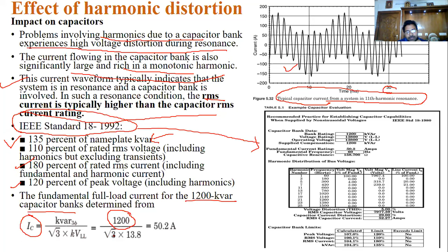So kVAR in 3-phase by √3 into KV LL. Now see this. What is this kVAR rating? This is the full load current for that kVAR capacitor. Load current of the capacitor is 1200 by √3. This is a 3-phase system, so that's why √3 into this phase-to-phase voltage VLL, line to line. Okay, for a 3-phase system. So this is the 50. You can calculate it. The current is like this.